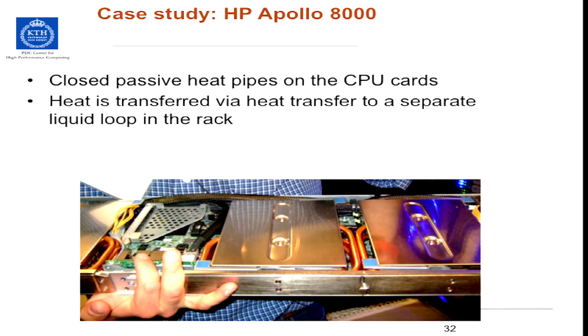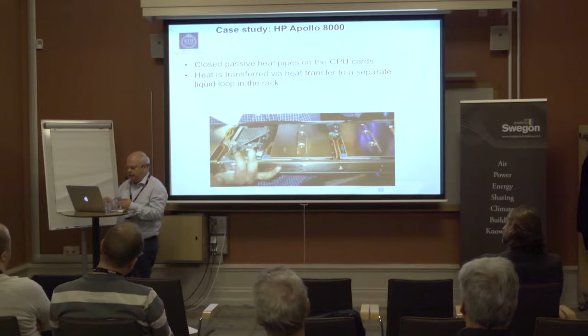Here you see a CPU board, and on the board there's a heat pipe going through all the active components. The heat is then transferred through this metal plate, metal to metal. So when you insert this into the rack, the heat is transferred to the rack's cooling loop by using this metal-to-metal connection - they clamp it into the rack and transfer the heat.